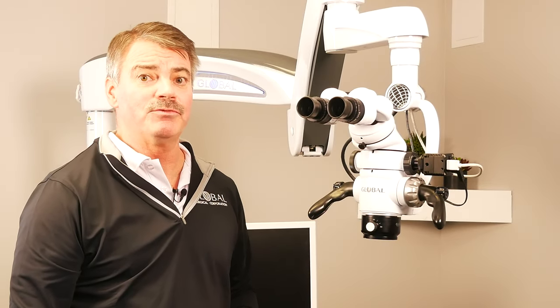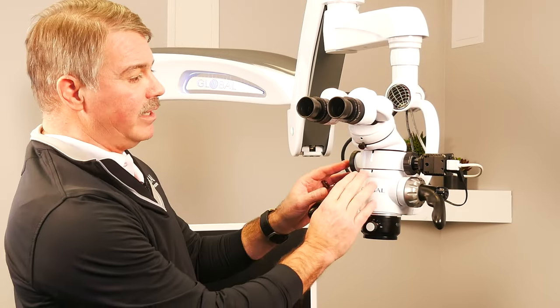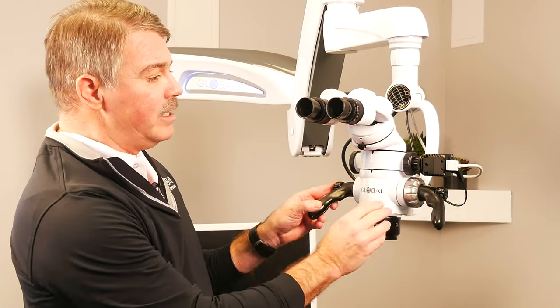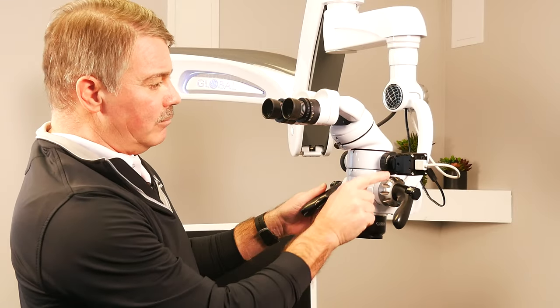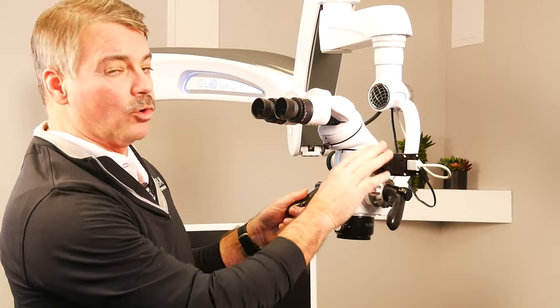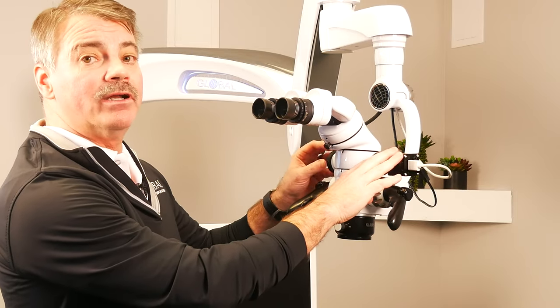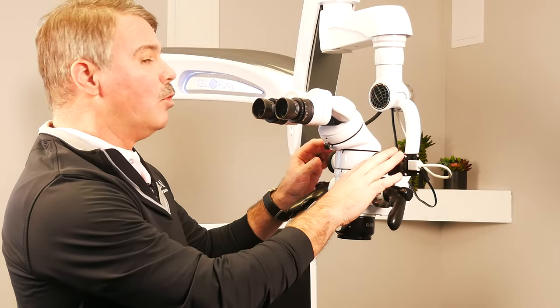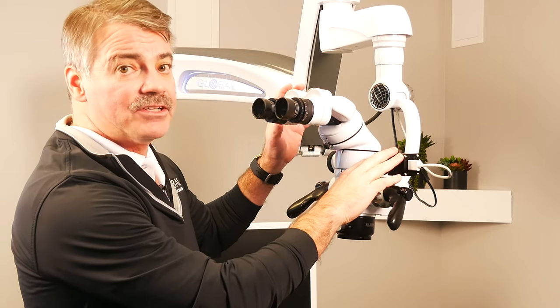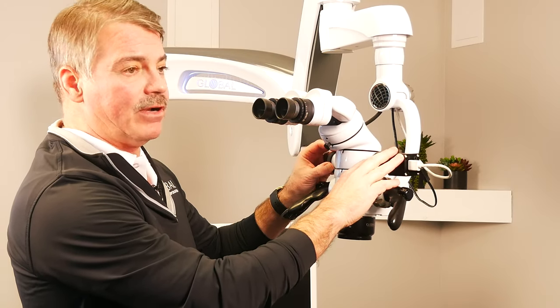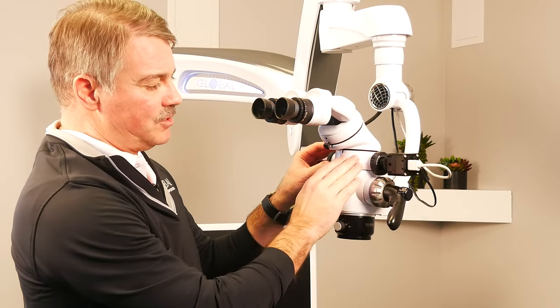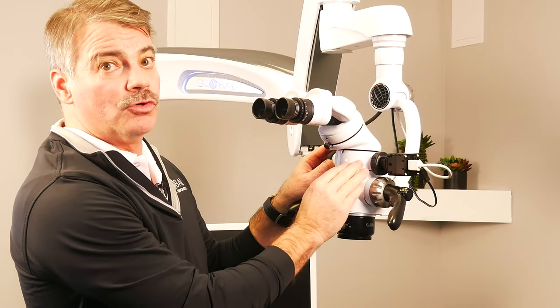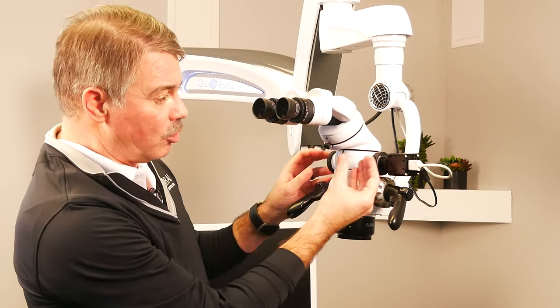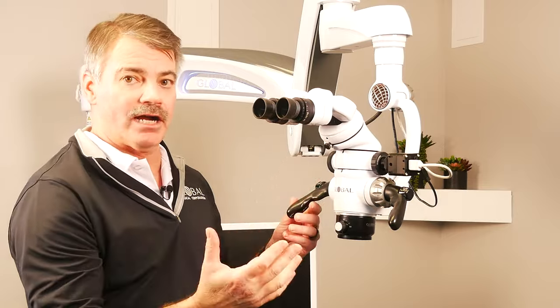One other note on the beam splitter itself is it can come in a single port or a dual port. A dual port, which we have here, would allow for a camera system and maybe a binocular observation system or a DSLR camera being attached to the same microscope at the same time. A single port, obviously then, is only one port that can actually be rotated from side to side depending on the doctor's dominant eye.